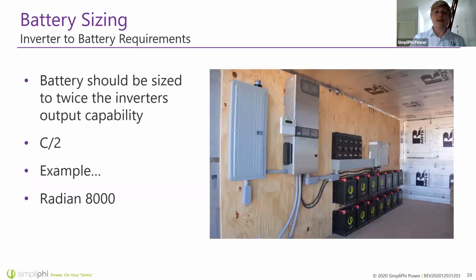Another important aspect of sizing is matching the inverter. For example, if you've got an 8 kilowatt continuous inverter like the Radian, you want at least 16 kilowatt hours of battery capacity. That's 5 PHI batteries per Radian 8kW inverter, which allows your batteries to provide the C/2 current the inverter needs if it wants to draw 8,000 watts continuously.